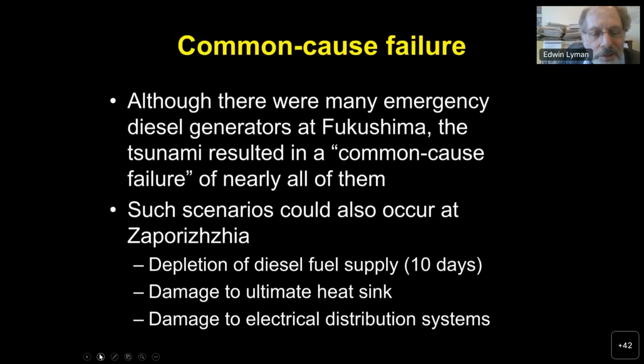So, it doesn't matter how many redundant backup systems you have. If something happens that disables all of them at once, then you are in trouble. And there are scenarios where that could occur at Zaporizhia. For instance, if they lost offsite power for a long period of time, those diesel generators are going to run out of fuel. And the site was stocking about 10 days worth of fuel.